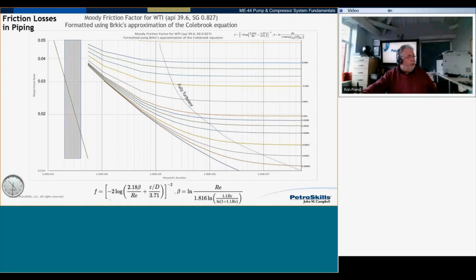Now, if you look at the bottom here, you'll see that the calculation is actually in 2 parts, and quite a few of them are in 2 parts. And if you look at the basic calculation here, you'll see that the friction factor minus 2 of the log 2.18 beta divided by the Reynolds number plus the relative roughness divided by 3.71 to the power of minus 2. All right, horrendous. Put it into Excel, guys. It's easy. You can do this, no problem. But what about this thing called beta? Well, beta is here.